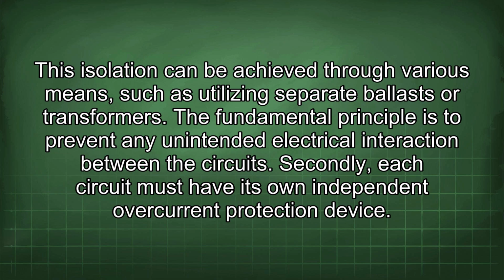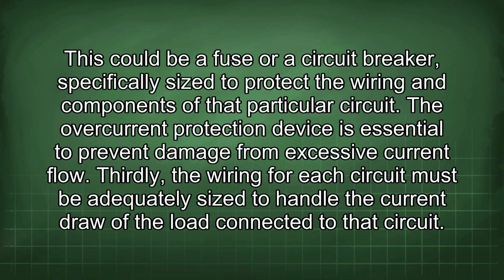Secondly, each circuit must have its own independent overcurrent protection device. This could be a fuse or a circuit breaker, specifically sized to protect the wiring and components of that particular circuit. The overcurrent protection device is essential to prevent damage from excessive current flow.